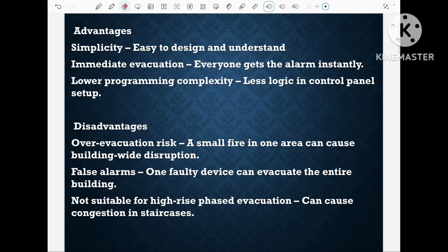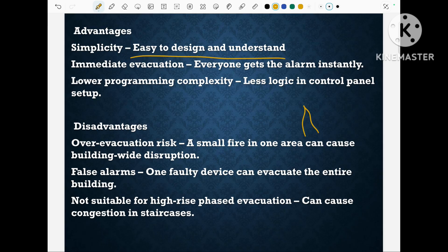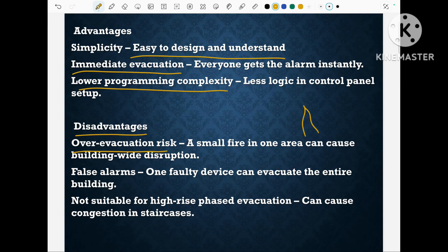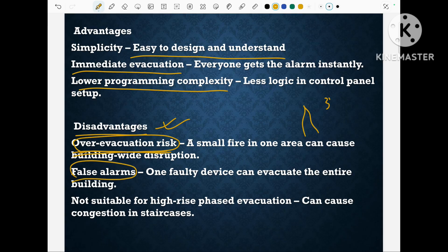Strategic evacuation is important in the fire alarm system and it can be done through zoning of sounder and visual alarm. In the one-out-all-out condition, if fire happens at one place then all sounders will ring together to evacuate the building entirely. This is good for a small building as it simplifies the design and enhances immediate evacuation with lower programming complexity. But for high-rise buildings the disadvantage is over-evacuation risk, and if a false alarm occurs, the full building will be in panic. It is not suitable for phased evacuation in multi-storey buildings.